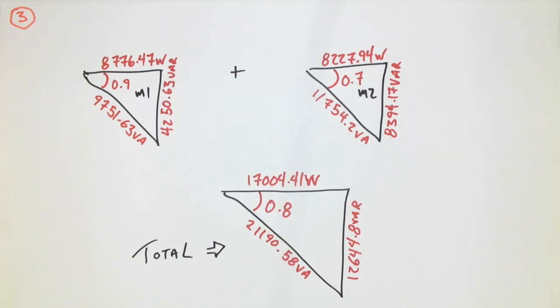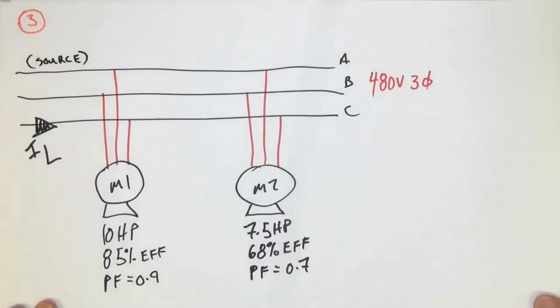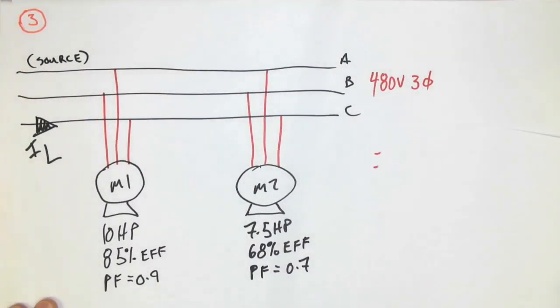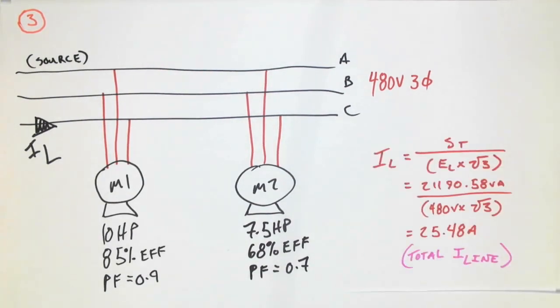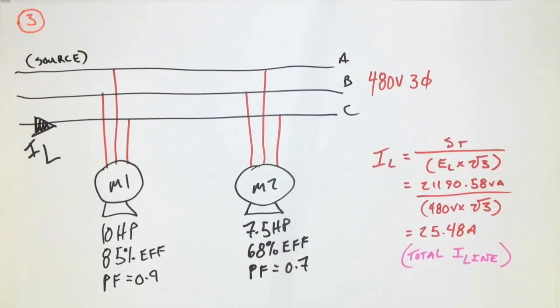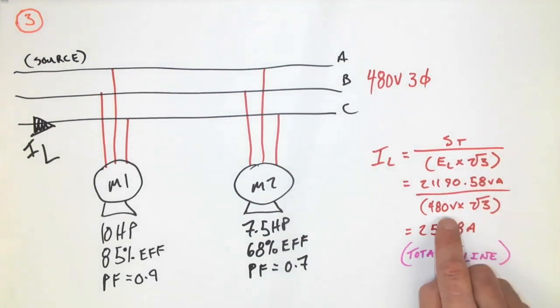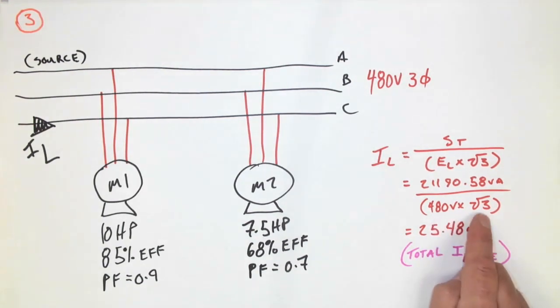Finally, the total for this particular circuit — the line current values, which were what was being asked for. Going back to the original question: 480-volt three-phase system, the total line current equals 25.48 amps, because we took the total S and divided it by the voltage — the line value times root three — to get just over 25 amps.